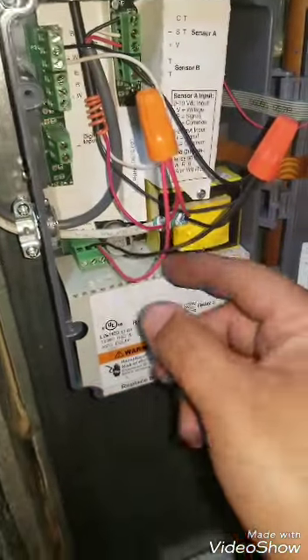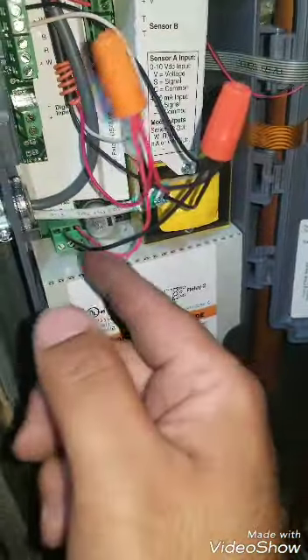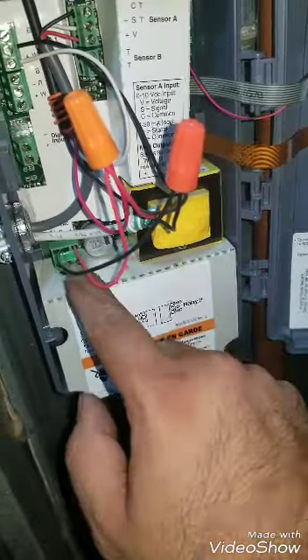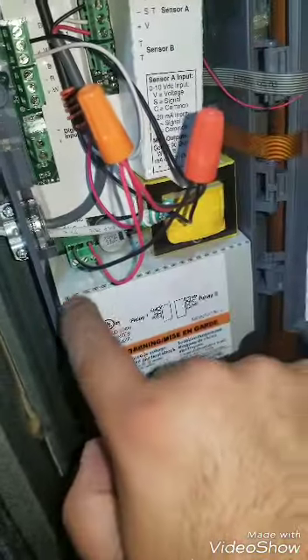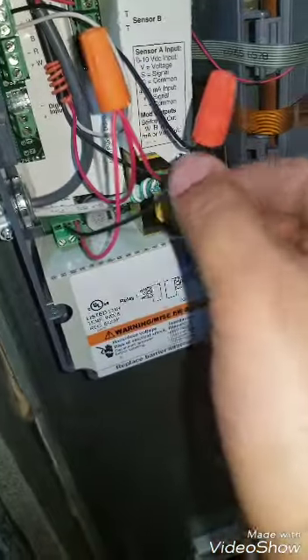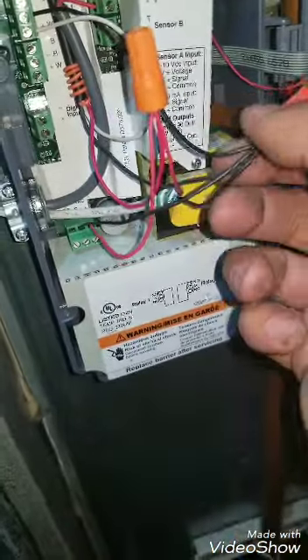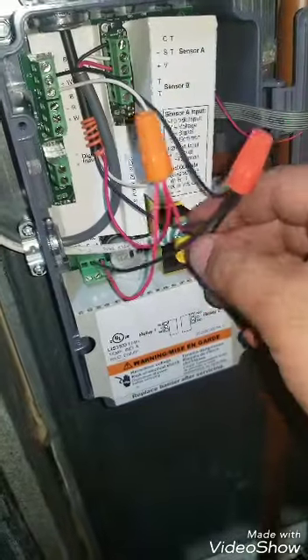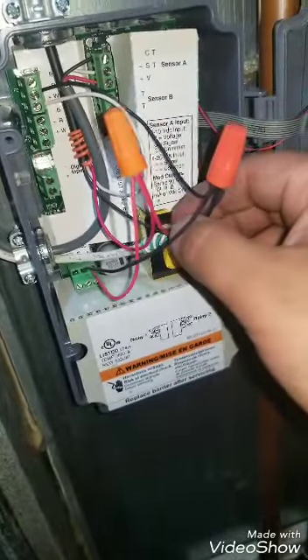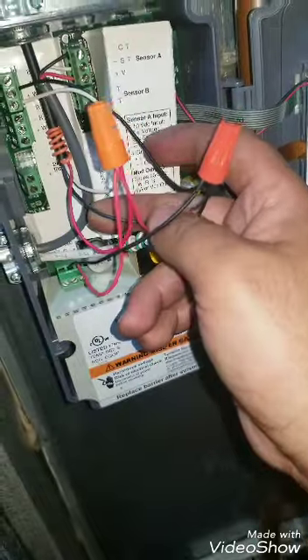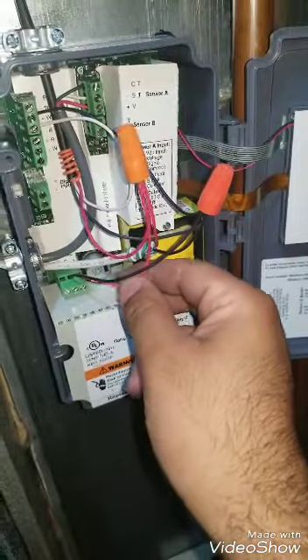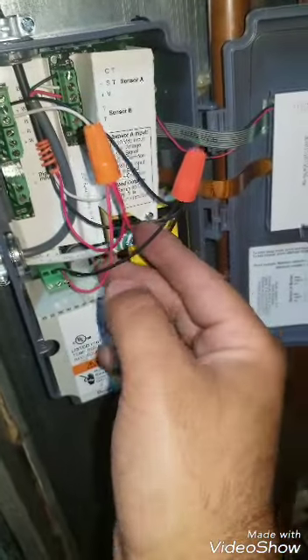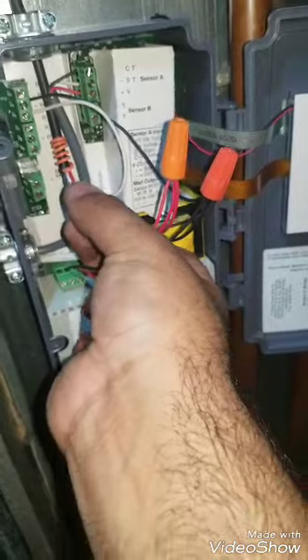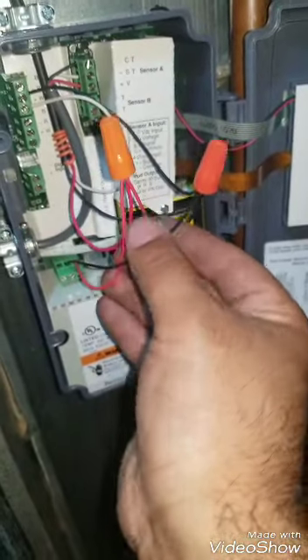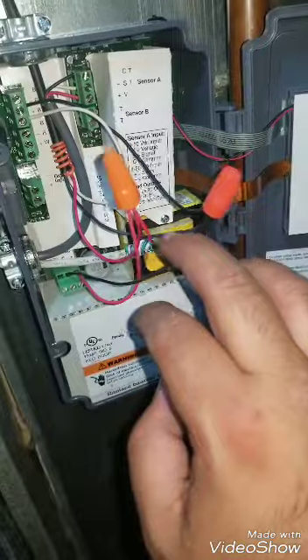Okay, so your terminations are as follows. I put two little pigtails, common and hot, right here. I don't like to put all these wires inside there, so I just make little pigtails, right? So this is common. Black is common. It's gonna pick up the common from the 24 volts, and it's also gonna pick up this common back here, which goes up to the Belimo. All right, black. And then the red, which is this one, it's gonna pick up the transformer, and it's also gonna power up my Belimo. So that's the 24 volts to the Belimo. Copy? 24 hot, 24 common.